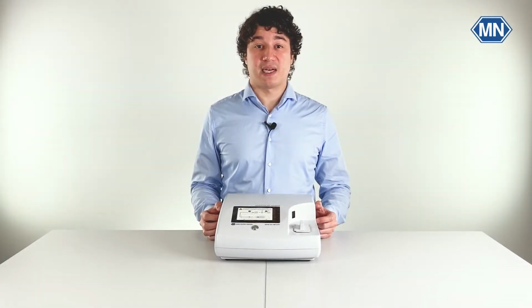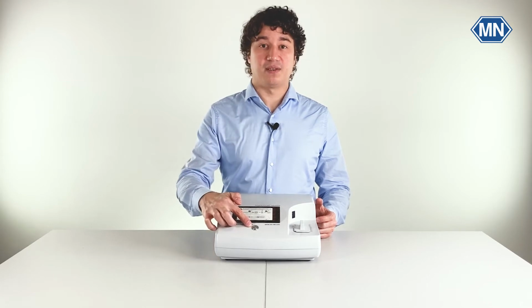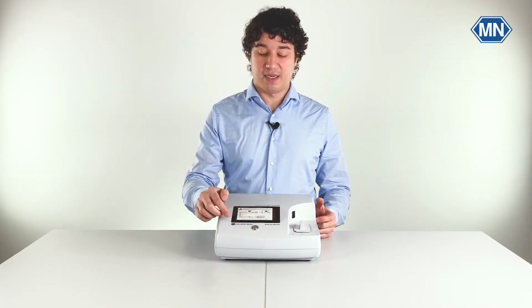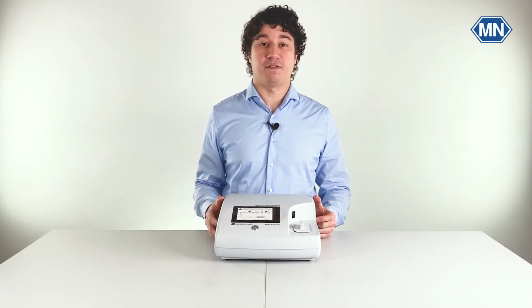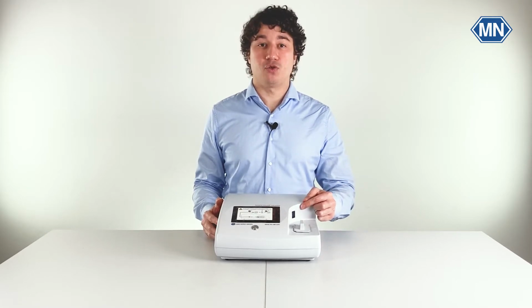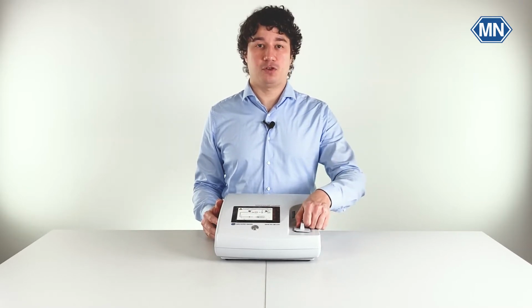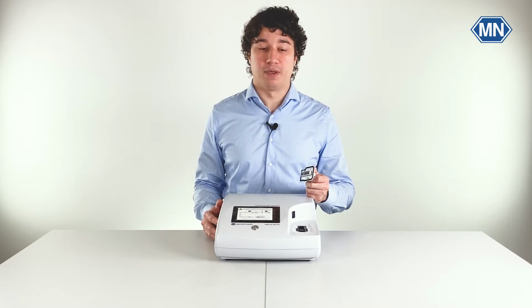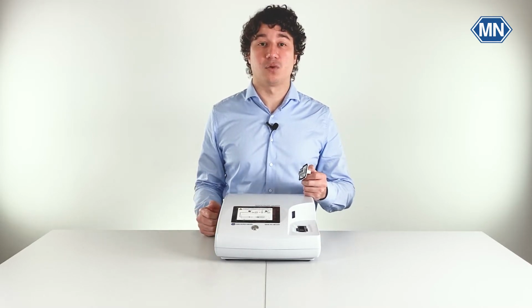The Nanocolor Advance comes with only one button here in the front that is used to switch on and off the device. Everything else can be controlled with this 5-inch touchscreen. It also has a 2D barcode scanner, as well as a cuvette shaft that is protected by this removable cover. Note that this is not used during measurements, as the device is completely insensitive towards stray light.